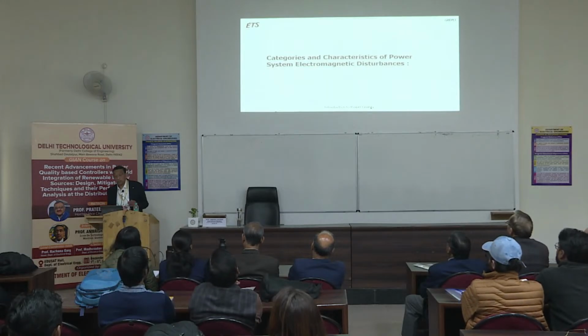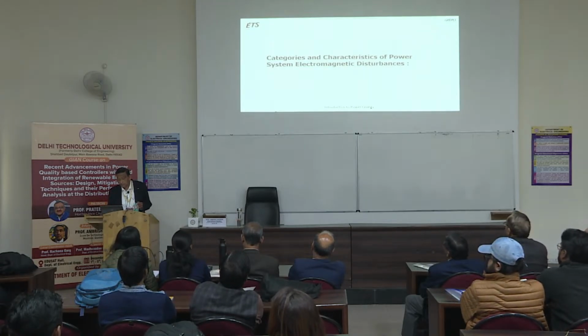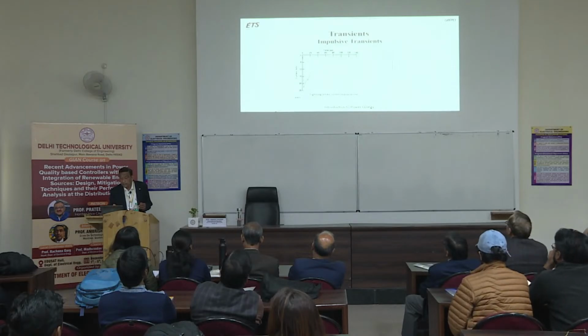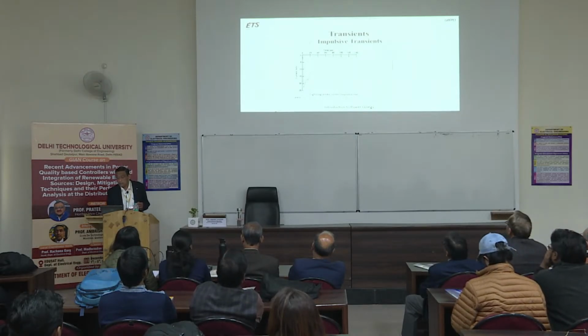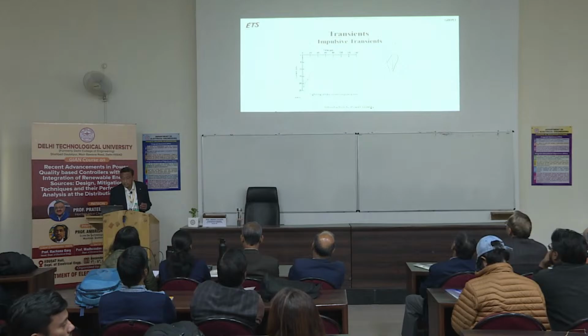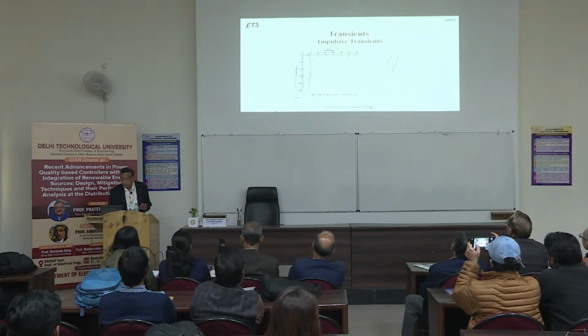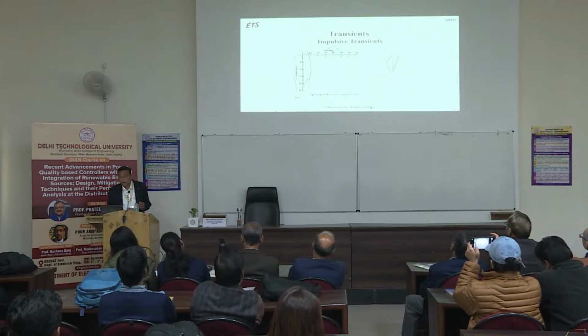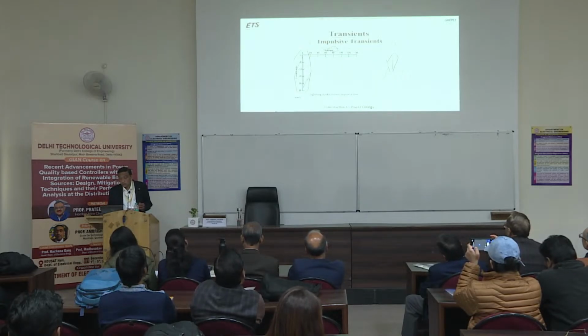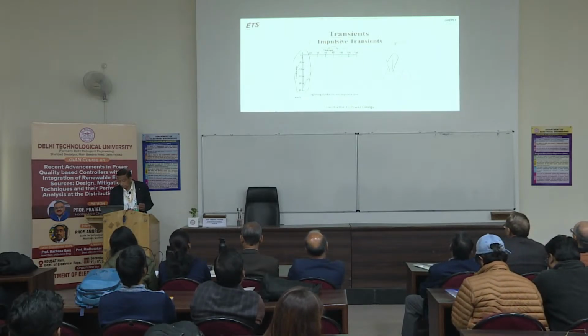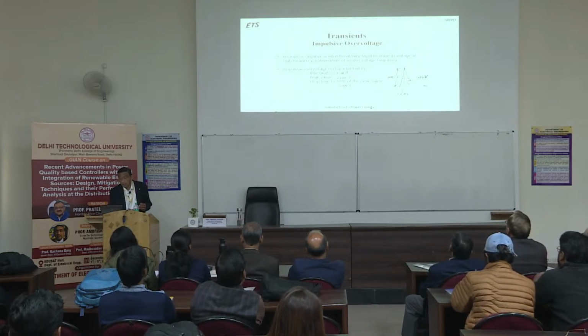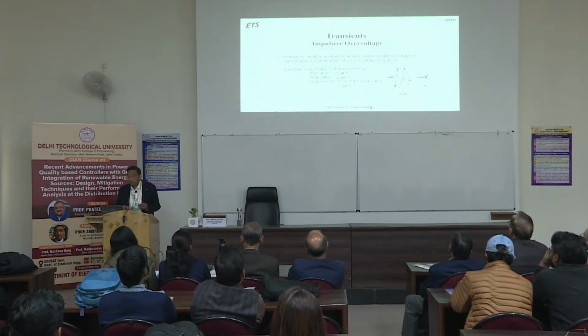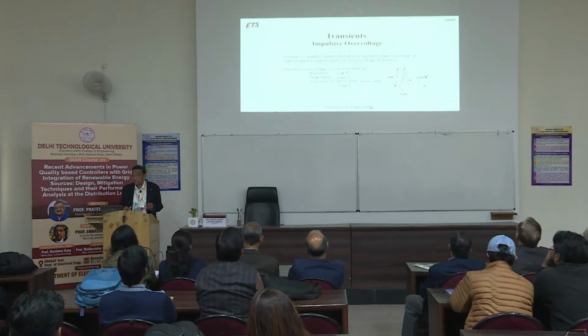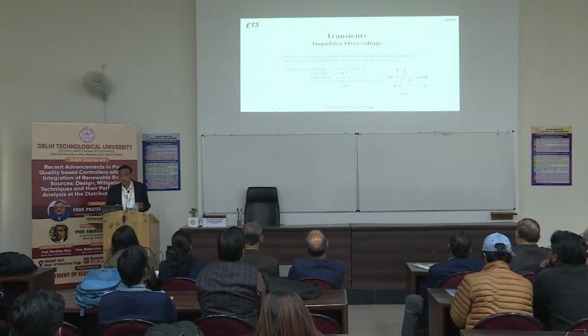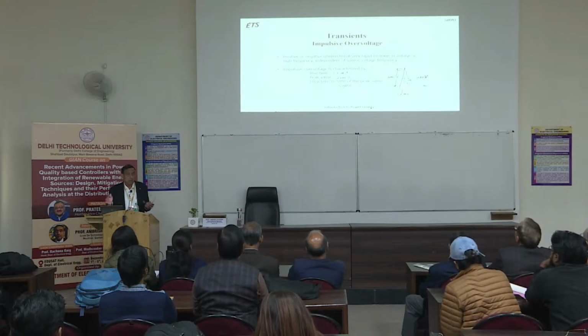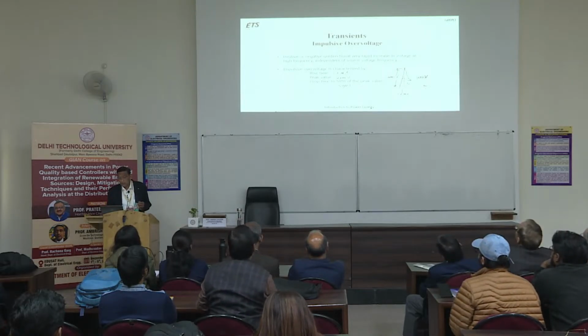Categories and characteristics of power system electromagnetic disturbances. First, the impulsive transient, you can see. In microseconds, you have 20 kiloamperes of current for a few microseconds. So this is an impulsive transient. Positive or negative, unidirectional, a very rapid increase in voltage at high frequency, independent of the source voltage frequency. Suppose you have 50 Hz or 60 Hz, but it has nothing to do with this. It is in microseconds, high frequency.